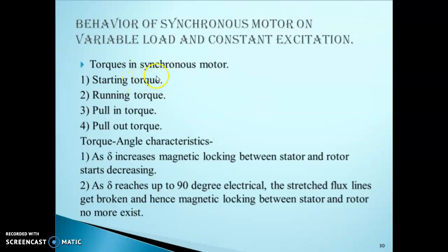Then these are the variable torques developed in a synchronous motor: starting torque, running torque, pull-in torque and pull-out torque. We will discuss them one by one. The starting torque is the torque developed in a synchronous motor at start when rated voltage is applied to the stator, and this torque is also called the breakaway torque. The next is the running torque. This is the torque developed by the motor under running condition.